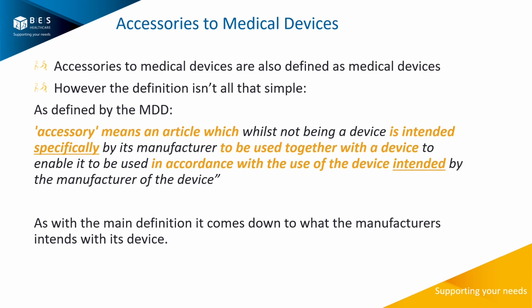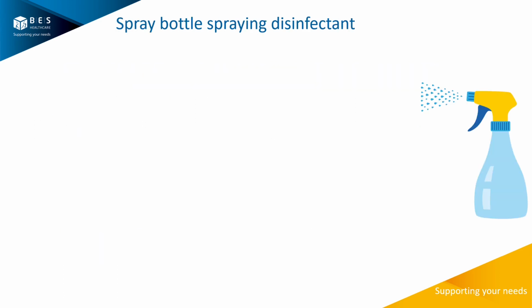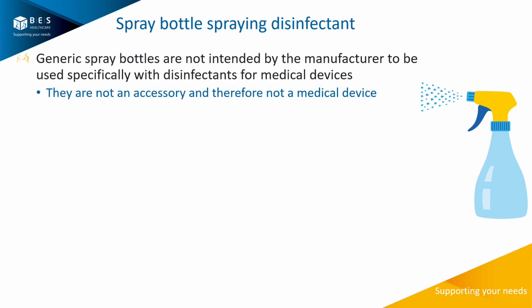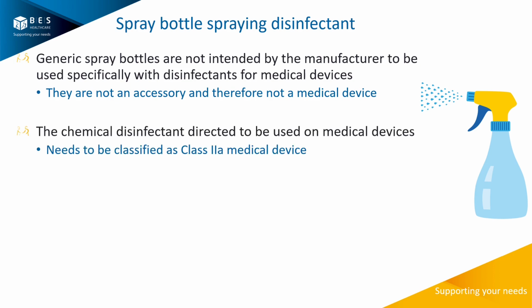So I'll just run through an example which will hopefully illustrate this. So let's take a spray bottle. Now you could use a spray bottle to spray water, you could use it to spray a medical device disinfectant. Now does the fact that it's being used in that way make the bottle a medical device or not? So if the manufacturer is just a manufacturer of generic bottles, they just say this is a spray bottle. It is designed to be used to spray liquids, and they don't have any specific intent around what kind of liquid is being sprayed. So because that's the case, just because you're putting a medical device, i.e. a chemical disinfectant in there, doesn't mean that the bottle suddenly becomes an accessory because the manufacturer is not making it to be an accessory. The chemical disinfectant directed on medical devices does need to be Class 2A, but not the bottle.